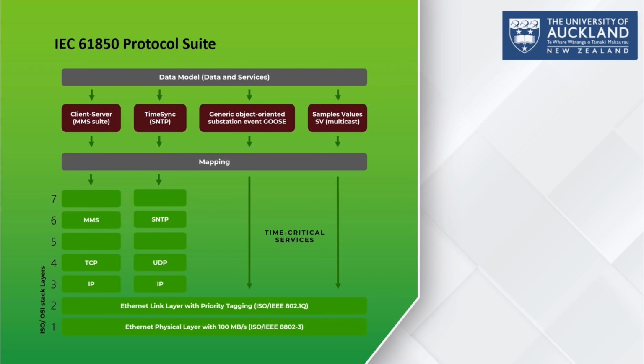The lower part of this diagram illustrates the communication stack of each data type. MMS messages travel through the MMS protocol, then through TCP/IP, and finally over the Ethernet. Similarly, SNTP messages travel via UDP, then IP, and then Ethernet.